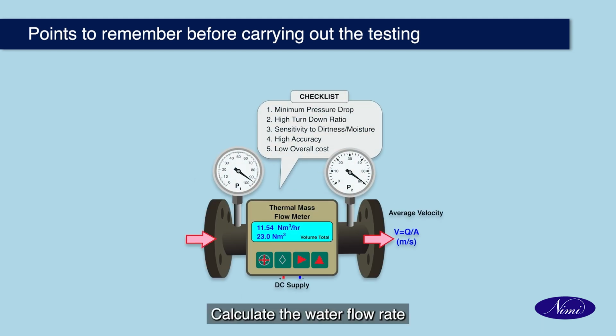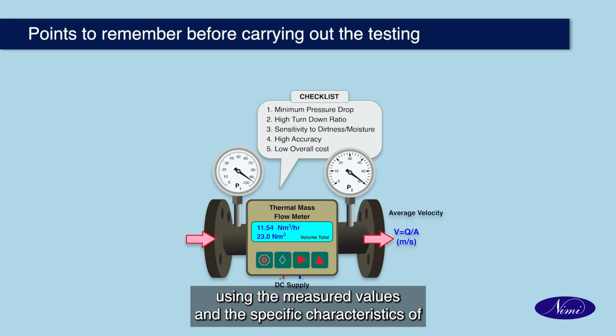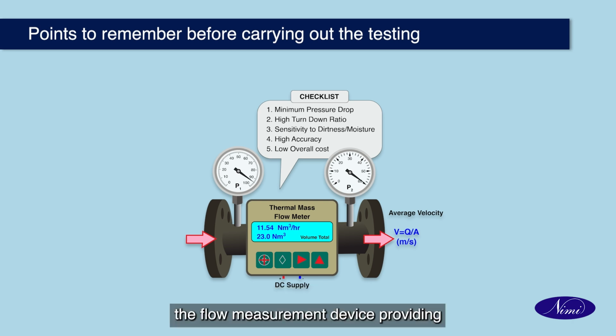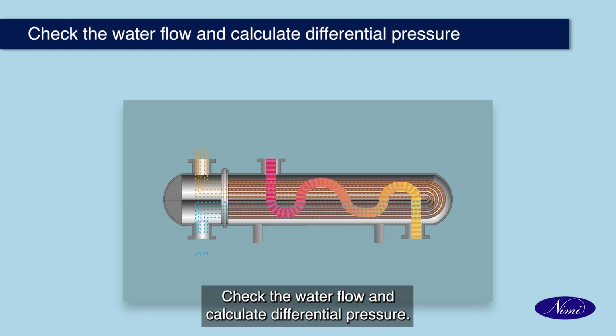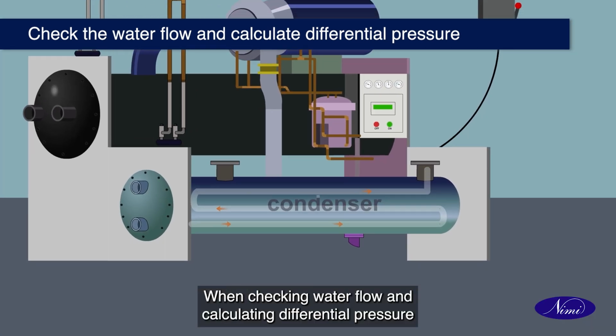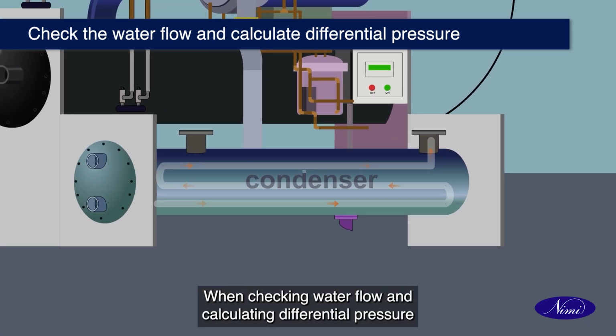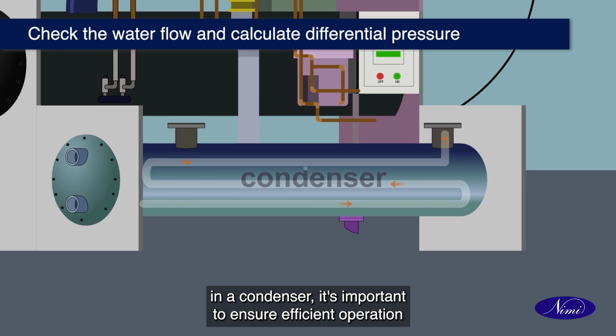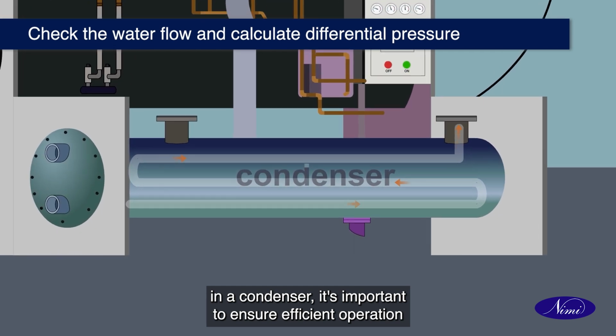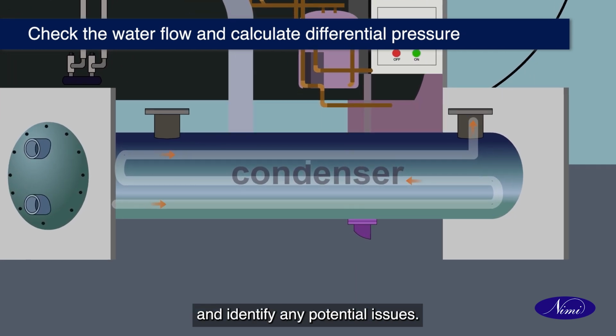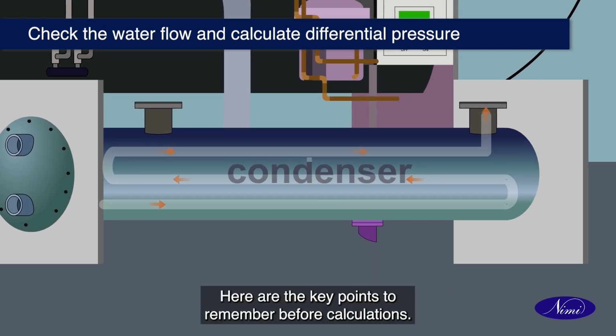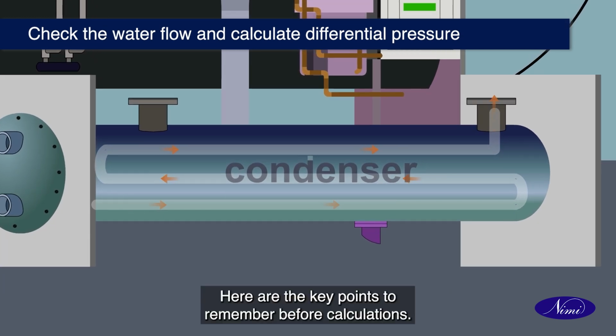Calculate the water flow rate using the measured values and the specific characteristics of the flow measurement device, providing insights into the overall performance of the water circulation system. Check the water flow and calculate differential pressure. When checking water flow and calculating differential pressure in a condenser, it's important to ensure efficient operation and identify any potential issues. Here are the key points to remember before calculations.